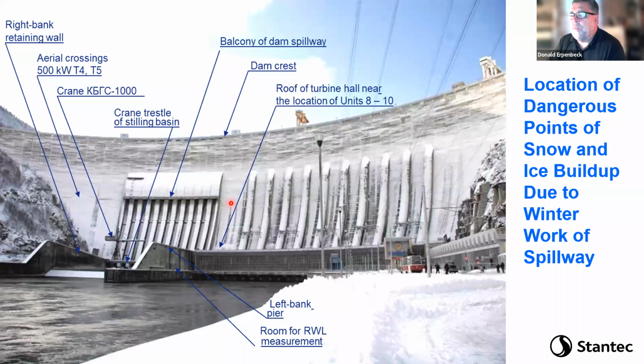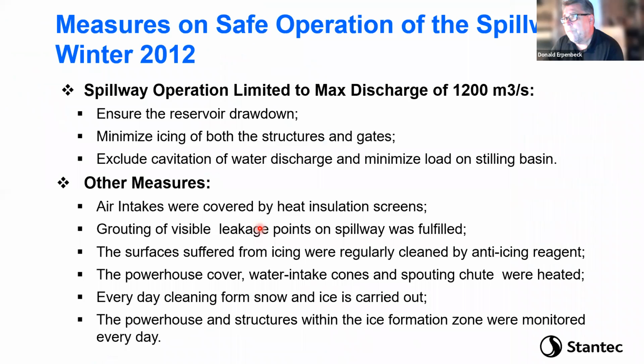One of the things I've told people is dams don't have a design life, turbines do. Turbine design life is typically about 30 to 40 years, and these units were coming up on their 40 years. We were hitting the end of their life, and then they put them into one of the most violent modes of operation you can put them into, and really triggered the event by the way they ran the machine and by not turning it off.